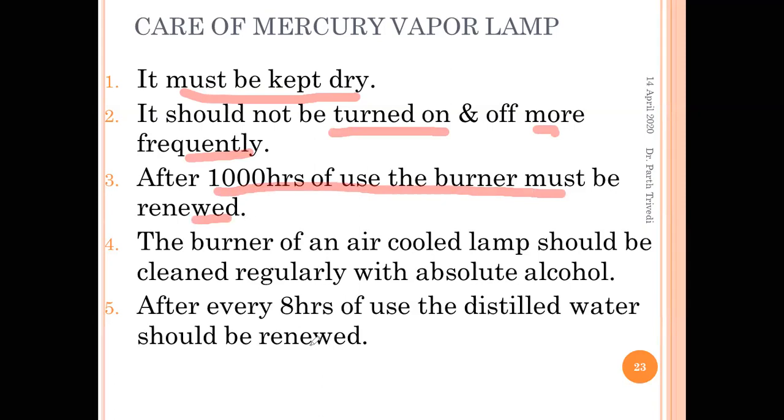Why? Because of tridymite formation. Okay, so this is one more major thing. The burner of an air-cooled lamp should always be cleaned with absolute alcohol so that the remaining impurities can be cleaned very easily. And after 8 hours of use, the distilled water should be renewed.